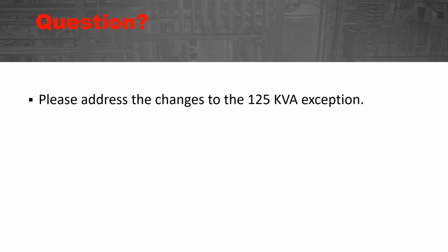It was also removed. In 70E, we had an exception pertaining to the 125 kVA transformer, and there was some confusion there, so the committee removed it. Actually, the way it was in 70E was not the same way it was presented in IEEE. And that's been gone for a number of years now, along with our default arc flash boundary of 4 feet. That has been changed. 70E, if you've been following it for a while, has gone through a number of changes every edition.